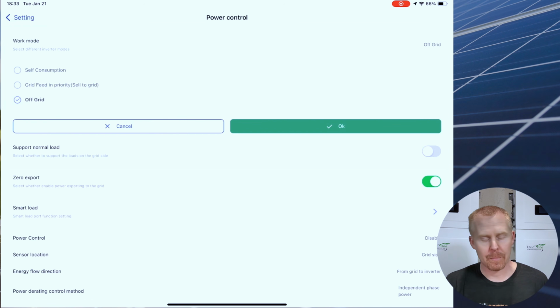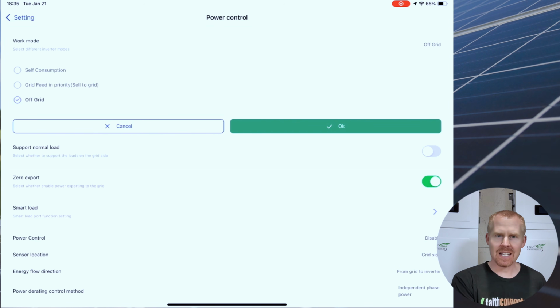Grid feed in priority is an option for you to sell back to the grid to be able to push excess power from your system, whether that's from solar or your batteries. In a self consumption mode or a sell to grid mode, you have the ability to connect current transformers, CT clamps, into your main panel and actually push power from your inverter through your AC input connection and supply power back into your main grid panel without it being directly connected to the output of the inverter.